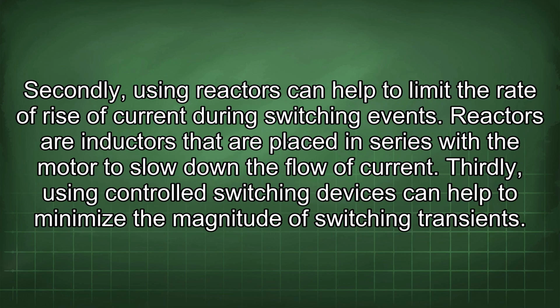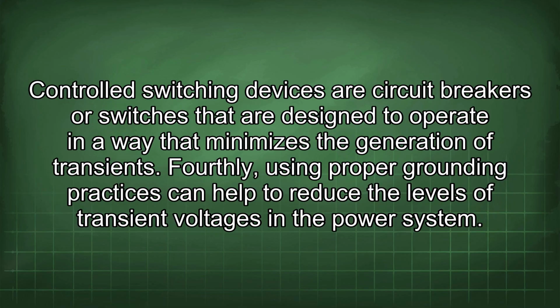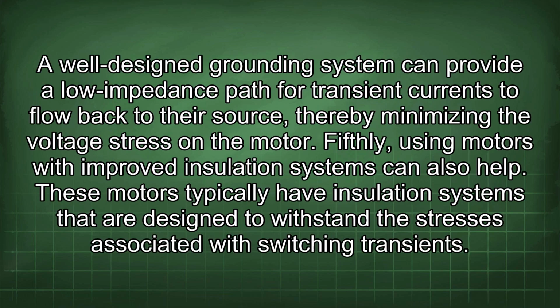Secondly, using reactors can help to limit the rate of rise of current during switching events. Reactors are inductors that are placed in series with the motor to slow down the flow of current. Thirdly, using controlled switching devices can help to minimize the magnitude of switching transients. Controlled switching devices are circuit breakers or switches that are designed to operate in a way that minimizes the generation of transients. Fourthly, using proper grounding practices can help to reduce the levels of transient voltages in the power system. A well-designed grounding system can provide a low-impedance path for transient currents to flow back to their source, thereby minimizing the voltage stress in the motor.